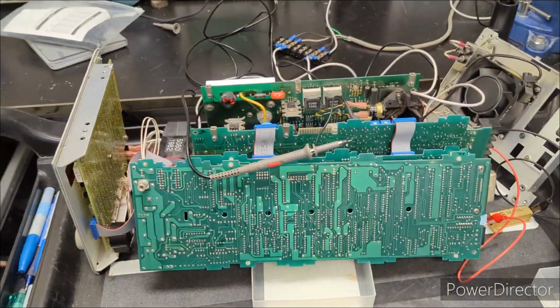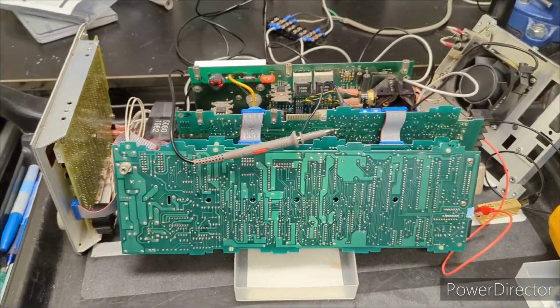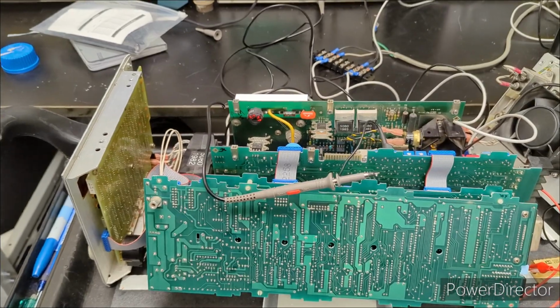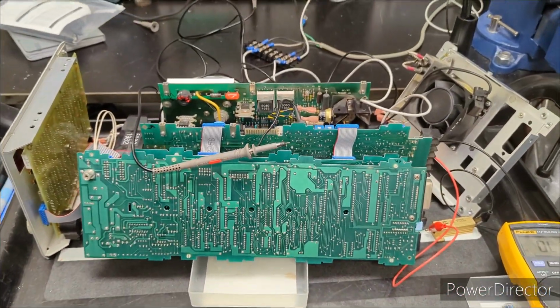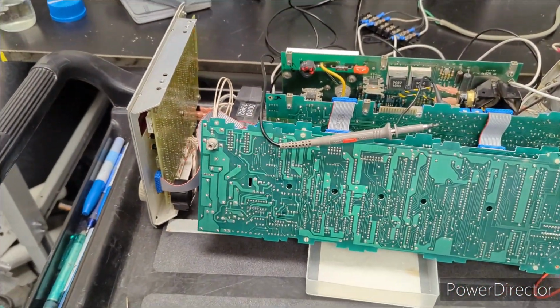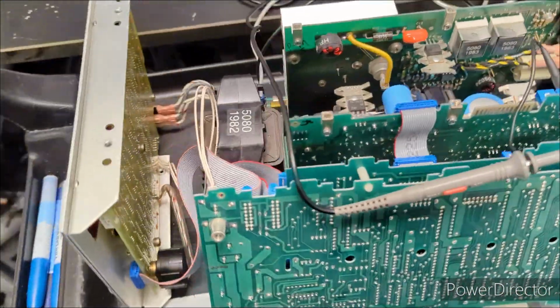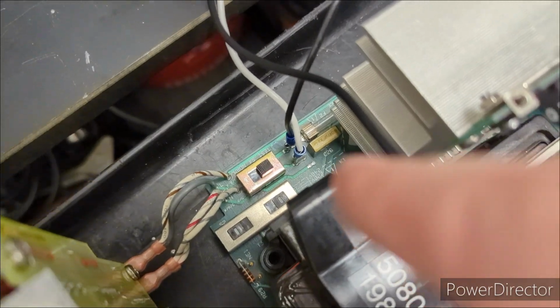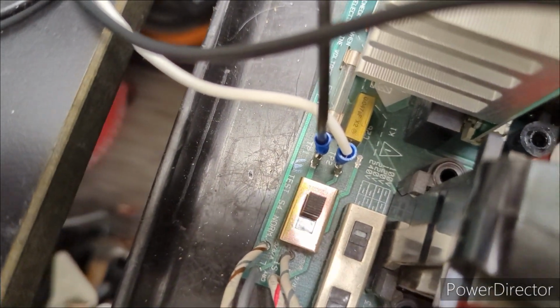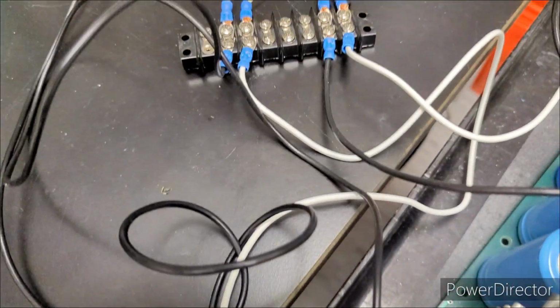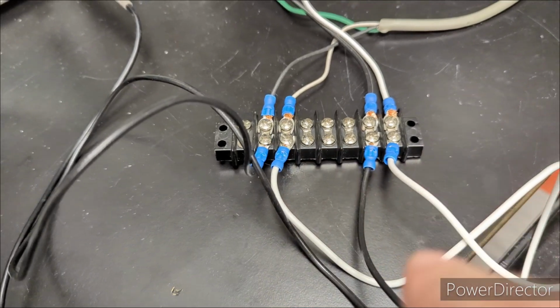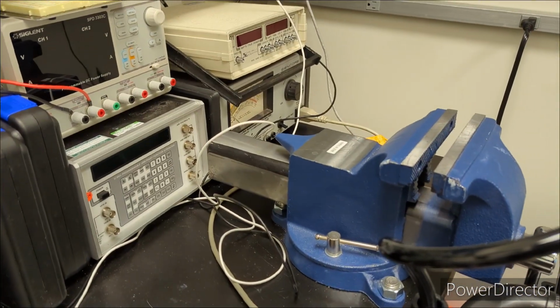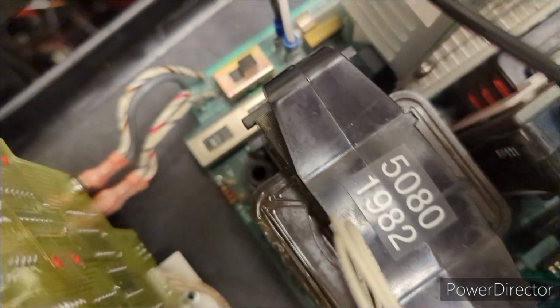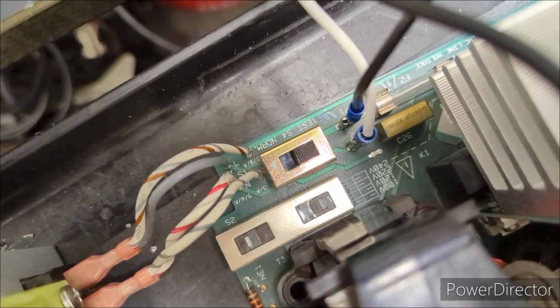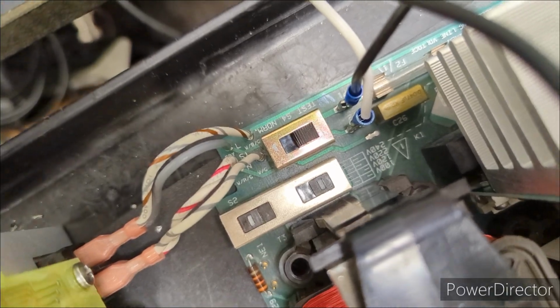Okay, so I've got the unit set back up in that main troubleshooting setup that the service manual suggests you use to troubleshoot the power section of the unit. Again, just to reiterate, with that setup they have you connecting an isolation transformer to these test points, TP1 and TP2. That's what I've got connected to that little terminal strip, which then goes on to my isolation transformer over there. They also have you set that switch, S4, from normal operation to test.